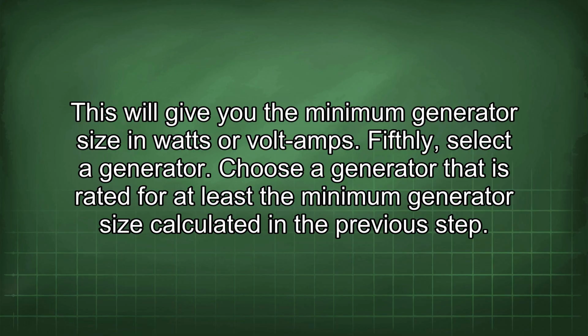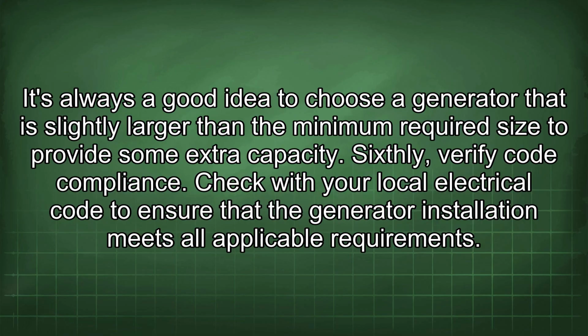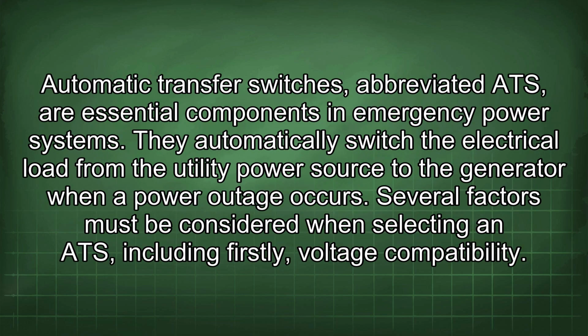Fifthly, select a generator. Choose a generator that is rated for at least the minimum generator size calculated in the previous step. It's always a good idea to choose a generator that is slightly larger than the minimum required size to provide some extra capacity. Sixthly, verify code compliance. Check with your local electrical code to ensure that the generator installation meets all applicable requirements. Automatic transfer switches, abbreviated ATS, are essential components in emergency power systems. They automatically switch the electrical load from the utility power source to the generator when a power outage occurs.